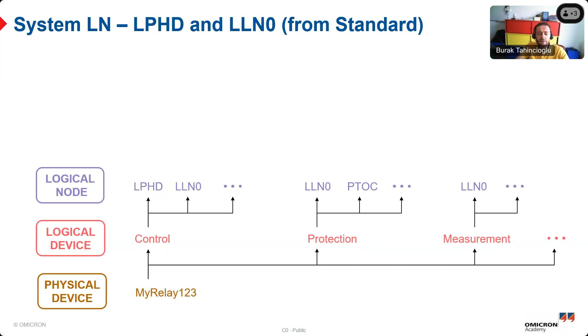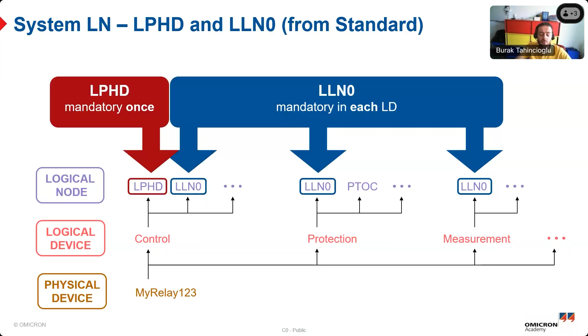Yeah. If you go next, Ali, we will see two things. When we define the logical nodes, we need to take care that there must be an LPHD logical node minimum at one logical device, and we must also have one LLN0 in each logical device. Okay, these are two basic requirements which we need to take care when we create the specification and virtual IEDs.